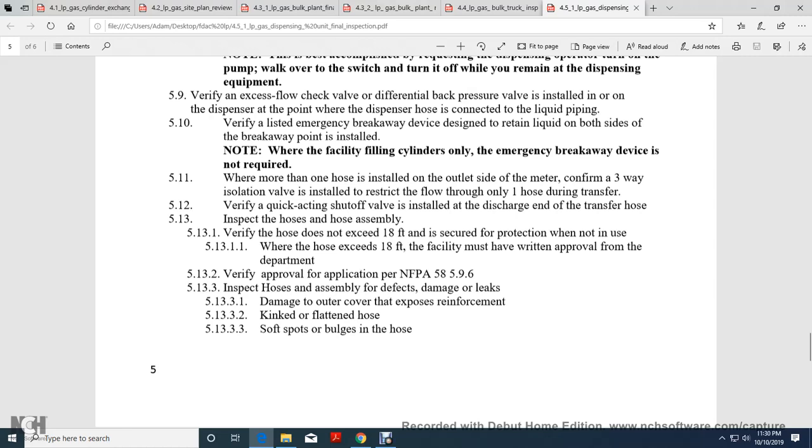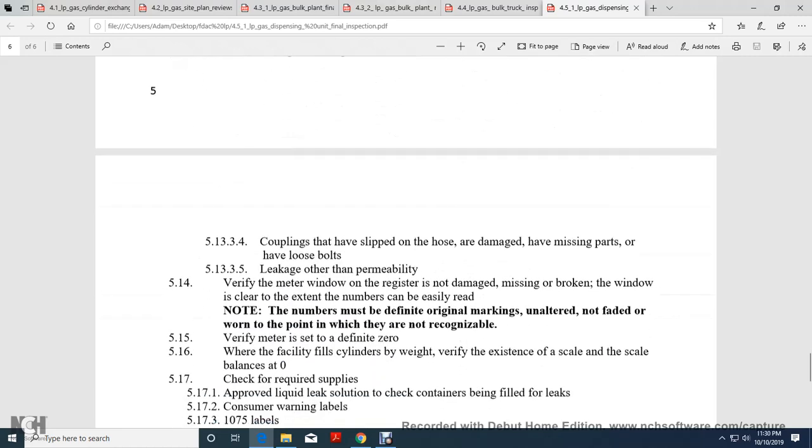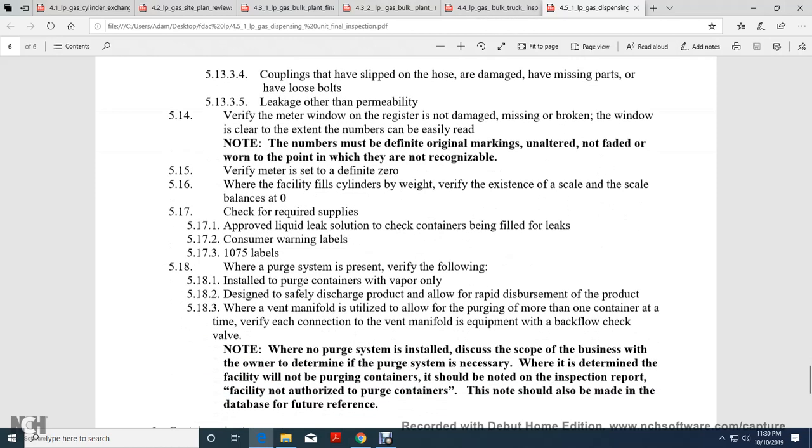Inspect the hose and hose assembly. Verify the hose does not exceed 18 feet, with secure protection when not in use. When the hose exceeds 18 feet, the facility must have written approval from the department, per NFPA 58 5.9.6. Inspect hose assembly for defects: damage, leaks, damaged outer cover, exposed reinforcement, kinks, flattening, soft spots, and bulges in the hose. Inspect couplings for slippage, damage, missing parts, and loose bolts. Verify the meter register is not damaged, missing, or has a broken window. Confirm numbers are clearly readable and unaltered, non-faded, and not worn to the point where they are unrecognizable.